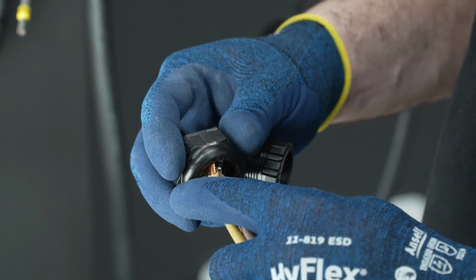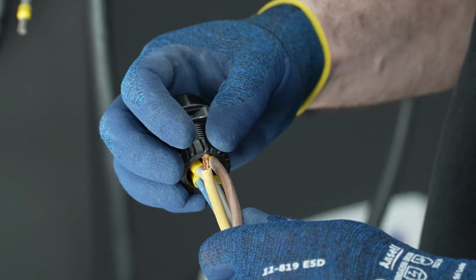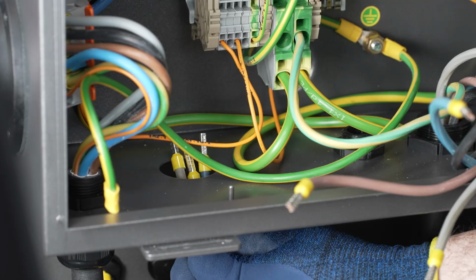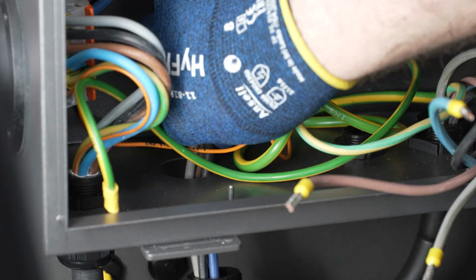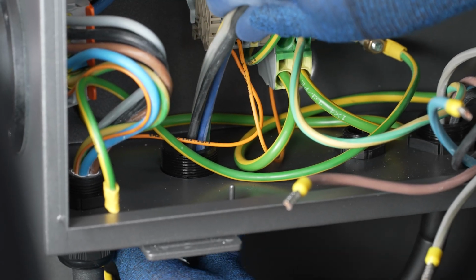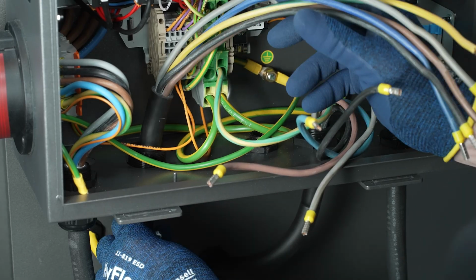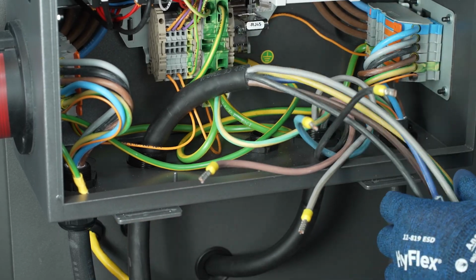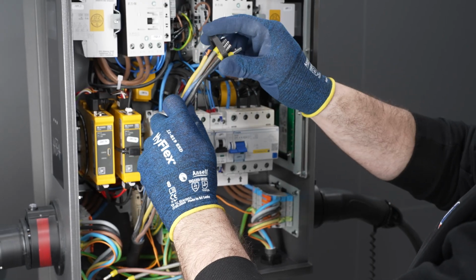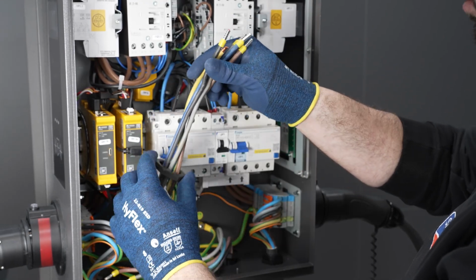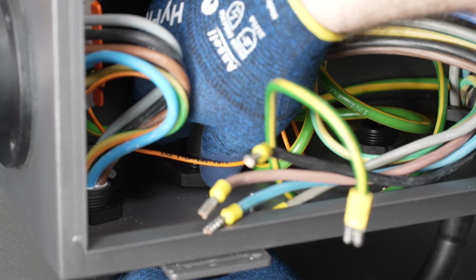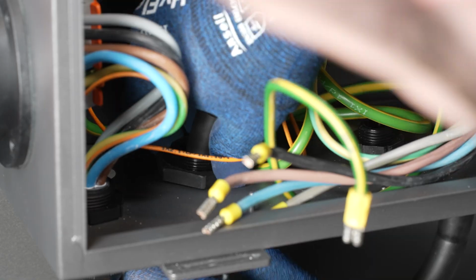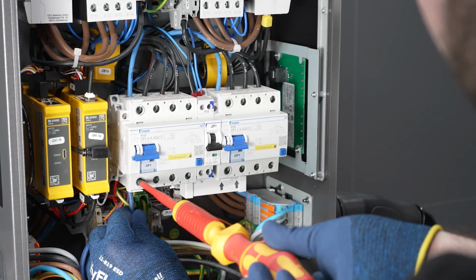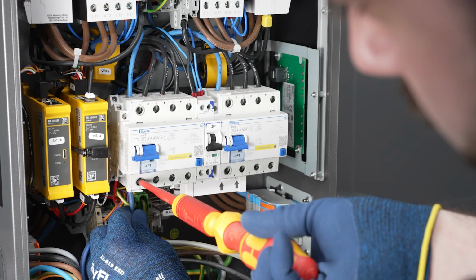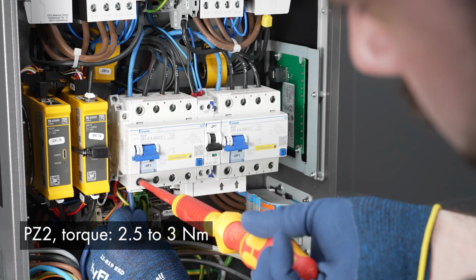Feed both AC cables through the cable glands into the product. To do this, loosen the two union nuts. Loosen M32. Connect the conductors N, L1, L2, and L3 to the respective residual current circuit breakers according to the labeling. Use PZ2 torque 2.5 to 3 Newton meters.